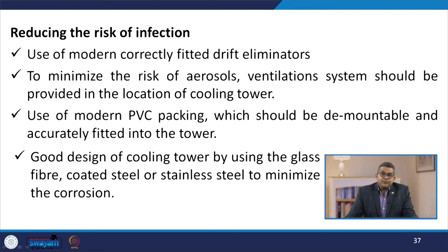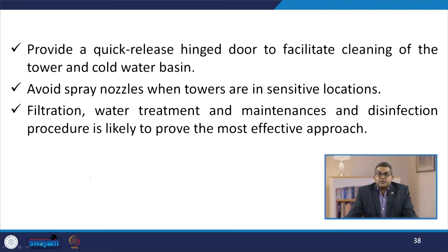To reduce the risk of infection: use modern correctly fitted drift eliminators; minimize the risk of aerosol by providing proper ventilation system at the location of the cooling tower; use modern PVC packing, which should be demountable and accurately fitted into the tower; use good design with glass fibre coated steel or stainless steel to minimize corrosion; provide a quick-release hinged door to facilitate cleaning of tower and cold water basin; avoid spray nozzles when towers are in sensitive locations; and employ filtration, water treatment, maintenance, and disinfection processes.